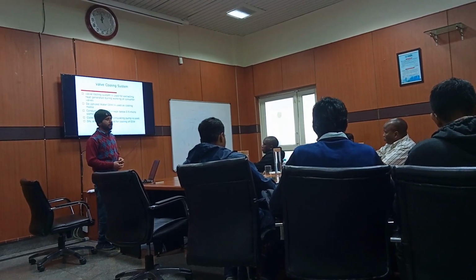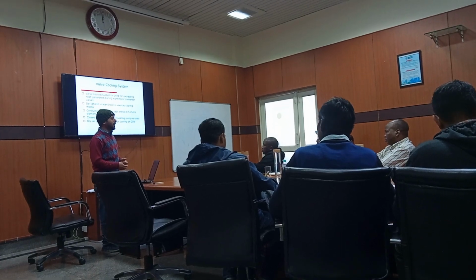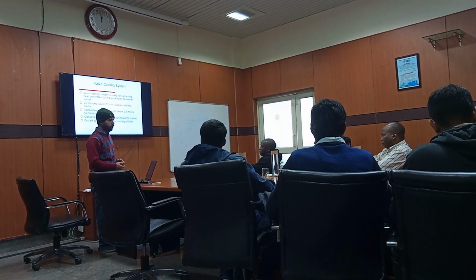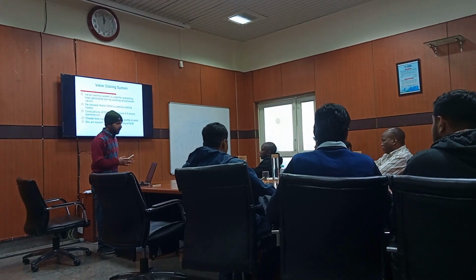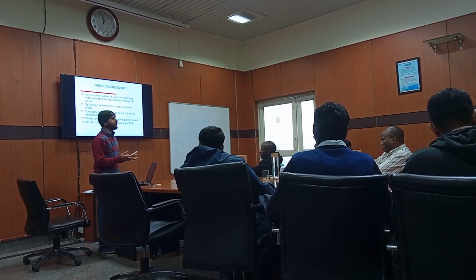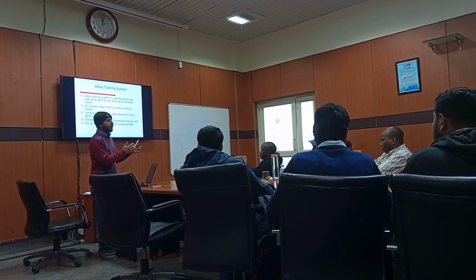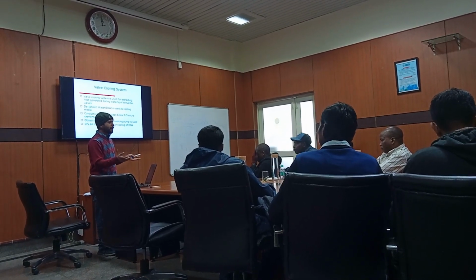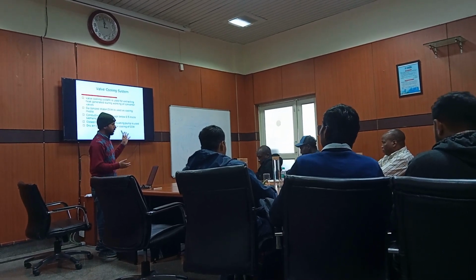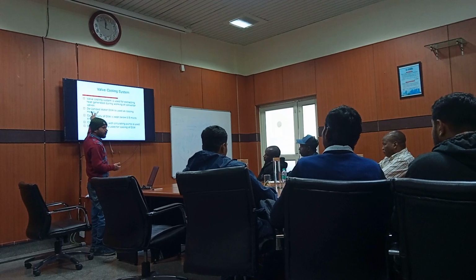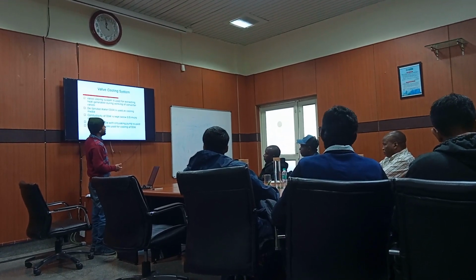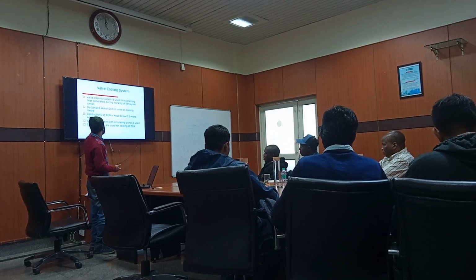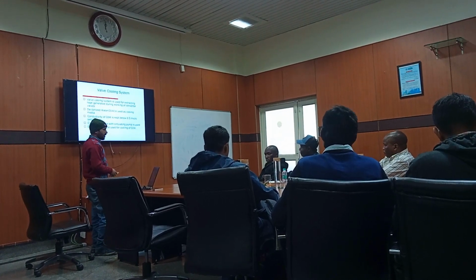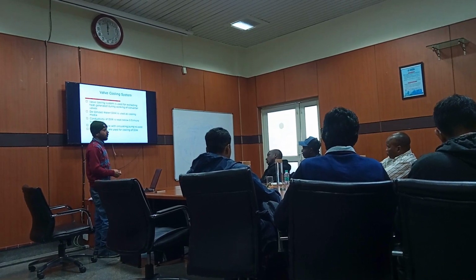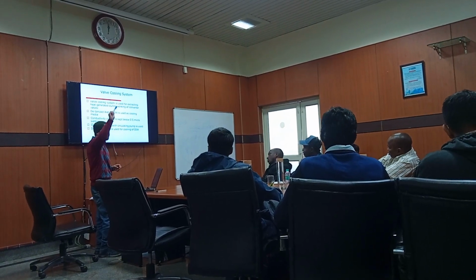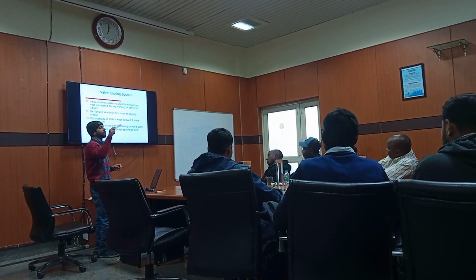It does not use normal water. The cations and anions in the water are removed because it flows inside the thyristors, which are conducting electricity. If normal water with a lot of ions were used, the water would become conductive. So it uses deionized water, and its conductivity is always kept below 0.5 microsiemens per centimeter. This is a closed loop cycle, meaning the water keeps running and should not come out.